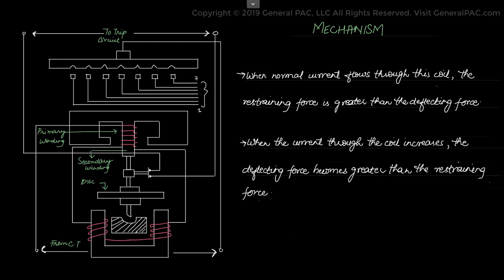That means the restraining force is greater than the deflecting force. But the current through the coil increases and after a certain level of current, the deflecting force becomes greater than the restraining force. As a result, the moving element starts changing the contact position in the relay. The trip circuit operates the circuit breaker which isolates the fault.